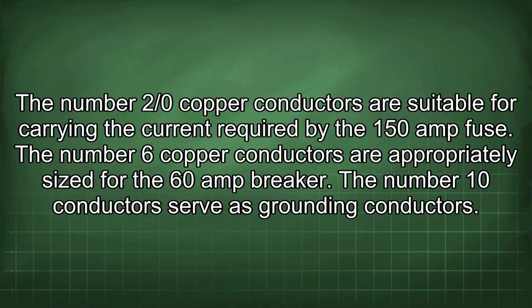The number 2/0 copper conductors are suitable for carrying the current required by the 150 amp fuse. The number 6 copper conductors are appropriately sized for the 60 amp breaker. The number 10 conductors serve as grounding conductors.